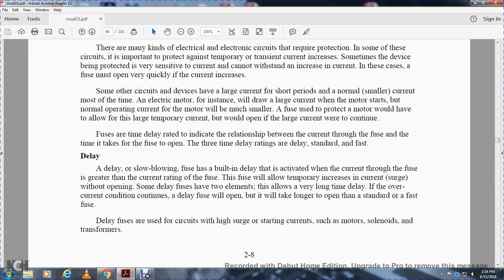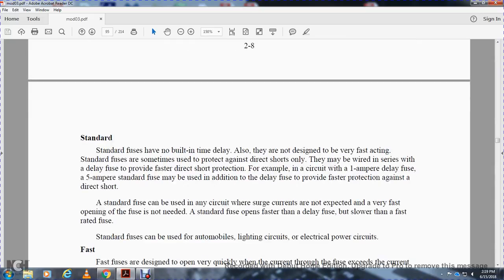Delay fuses have two elements that allow a very long time delay when an over-current condition occurs. If the condition continues, the delay fuse will open, but it will take longer to open than a standard or fast fuse. Delay fuses are used in circuits with high surge and starting currents, such as motors, solenoids, and transformers. Standard fuses have no built-in time delay, also they are not designed to be very fast acting. Standard fuses are sometimes used to protect against direct shorts only. They may be wired in series with a delay fuse to provide fast short-circuit protection. For example, a circuit with a 1-amp delay fuse and a 5-amp standard fuse may be used - in addition to the delay fuse - to provide faster protection against shorts.